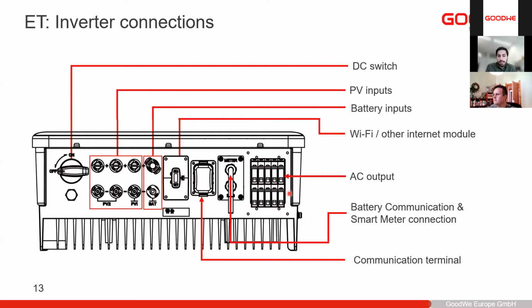And lastly, we have the AC output. Here you might notice that we have two different AC outputs. You have one here and one here. That means that one AC output is the standard AC output going to the grid, and the other one is the backup output. I explained the backup output a bit in the first module. In case the grid fails, this output will turn off and not be active, but the backup output will still be active. It's important when you install it in the house that you wire it properly, so that you have two different 3-phase connections, and that you make sure which loads you have connected to which connection.